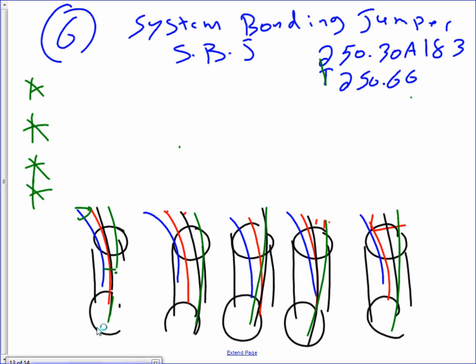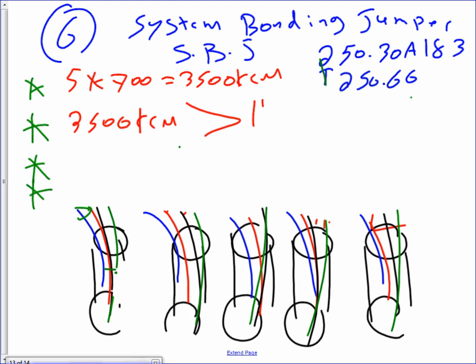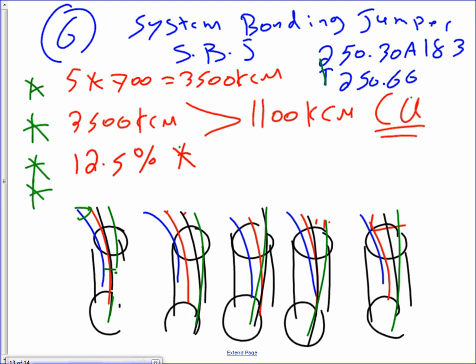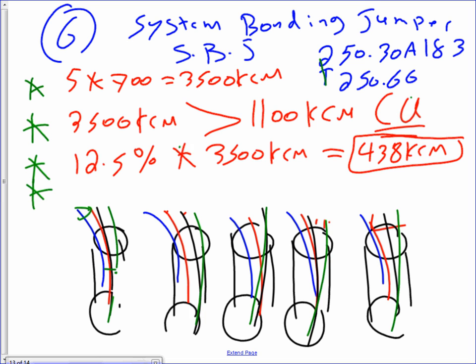Good. The last thing we need to size for this baby is the main bonding jumper. The main bonding jumper, gentlemen, you do the same thing. You take the 5 multiplied by 700. That will get you a healthy 3500 kcm. Since the 3500 kcm is more than 1100 kcm copper, this is your copper, now we will trigger the requirement of 12.5% multiplied by 3500 kcm. If you do the math on this, you end up with 438 kcm. And I don't know about you, but they don't make 438 kcm in the market. It's not standard.